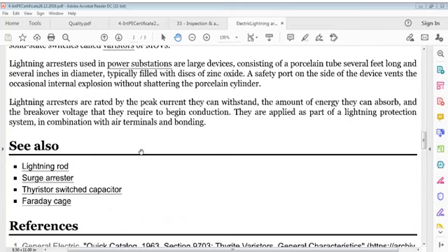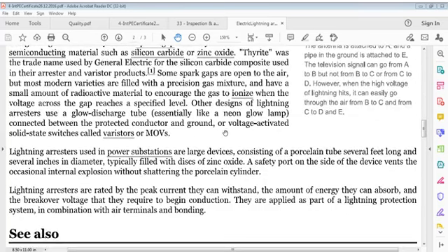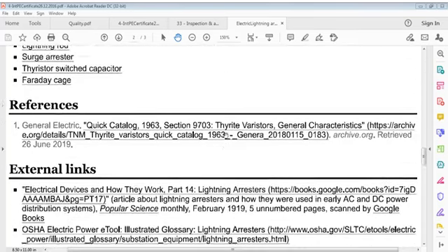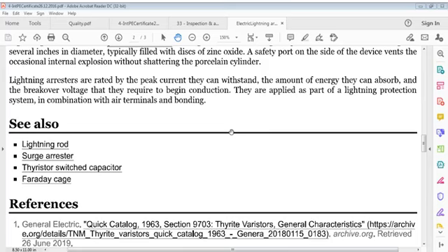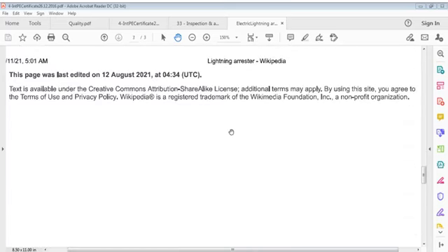Lightning arresters are rated by the peak current they can withstand, the amount of energy they can absorb, and the breakover voltage that they require to begin conduction. They are applied as part of a lightning protection system in combination with air terminals and bonding. So this is what we have gone through. This page was updated on, let me see, yes, 12th August 2021.